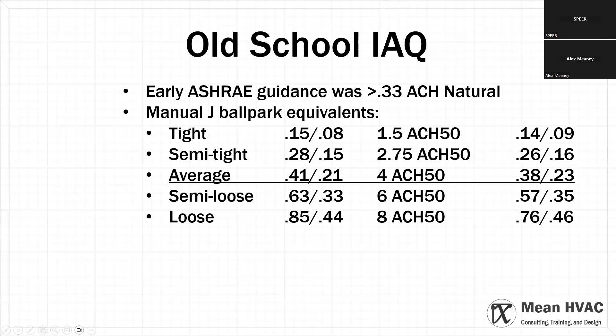Speaking of ventilation, which I will often jokingly call mechanical leakage because we use exhaust only ventilation from time to time. The problem with Wrightsoft, Elite, Cool Calc, the whole lot of them is they aren't breaking down their ventilation calculations. All of them have selectable ASHRAE ventilation standards, and then they do the math and spit out the ventilation number, which is great. And we want to trust it. That's cool.